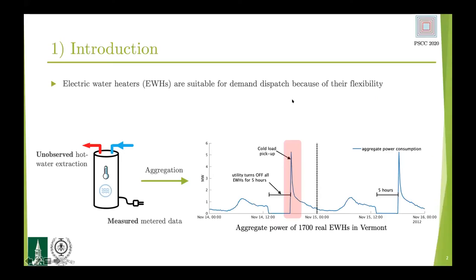If you look at large aggregations of electric water heaters, we know that their power consumption varies depending upon the time of day. Mornings are expected to be a large power consumption period because of larger water draws compared to the afternoons. The second thing is the effect of utility control, such as the data collected by a local utility in Vermont for about 1,700 electric water heaters. In this demand response program, the entire population was forced off for about five hours, and we're all familiar with the problem of cold load pickup. These two reasons motivate us to work on this problem.